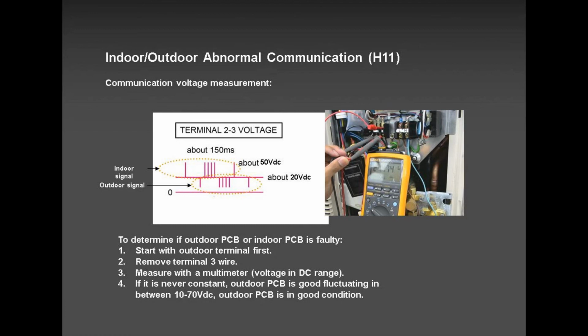Troubleshooting. Now remember, we never spoke about error codes in single zone. We did mention how to pull the error codes. It's the same that applies in multi-zone. Okay? You will use the remote controller and it has a check button. You press, you do the same style the way I explained to you with the single zone. And again, H11 is communication error for both multi and single.